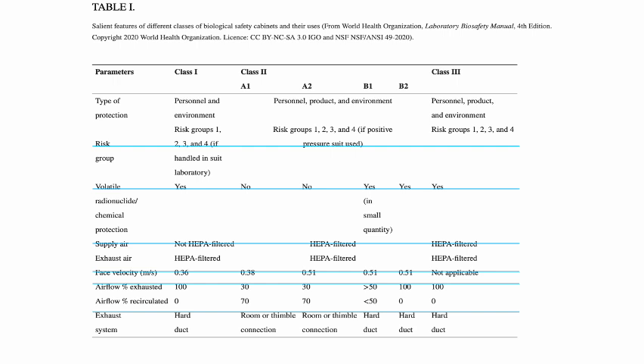This includes the type of protection that they provide, and the risk groups that can be manipulated or worked with in that class of biosafety cabinet. The third parameter is whether the biosafety cabinet can be used for volatile radionuclide or chemical protection. Fourth is the supplied air and exhaust air: is it HEPA filtered or not? And next is the face velocity.